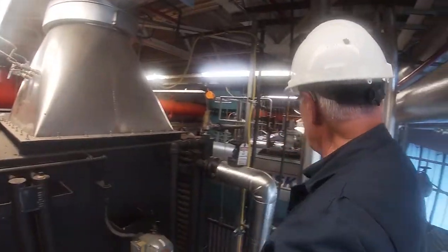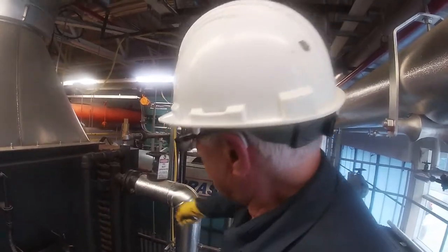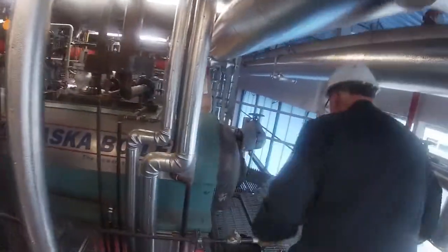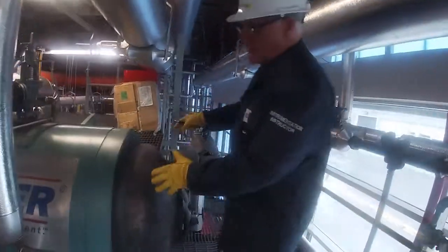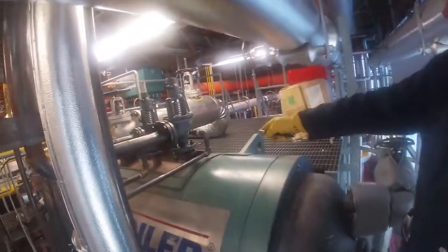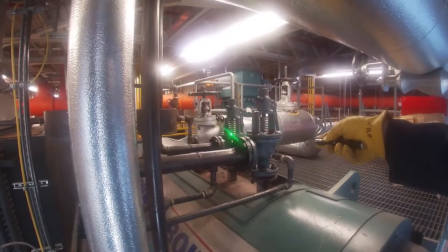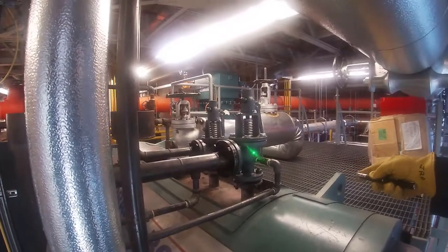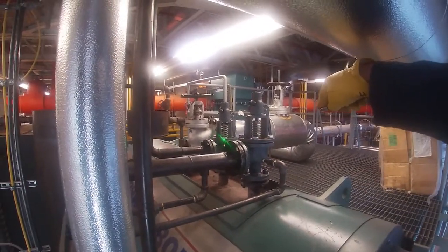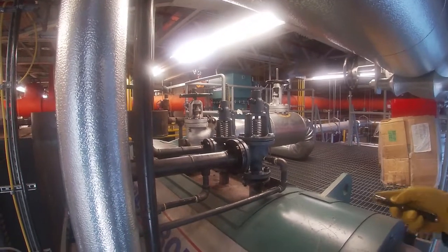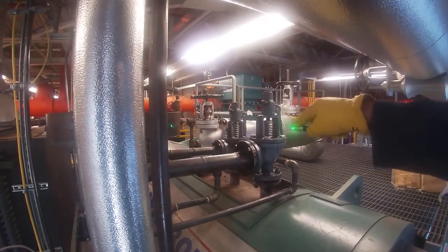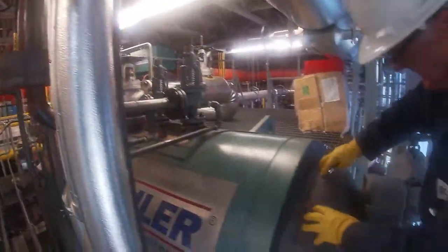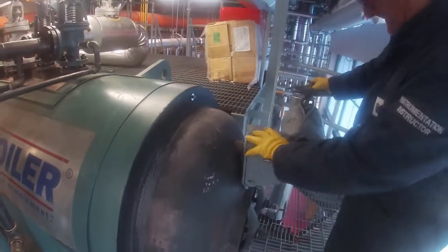Now, what we're going to do next is go downstairs, but before we do, while we're up here, this is the steam drum. You can see the safety valves there, and the non-return valve right there. This one is set for 305 PSI. This one is set for 300 PSI. And then you can see that the steam will come out on here, and then there are drip legs and a condensate drain sitting on there. The drum itself is sitting in here.